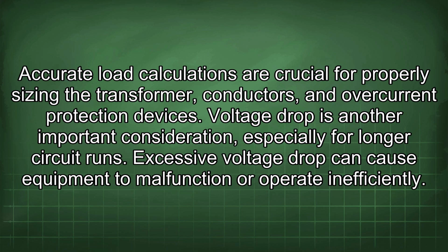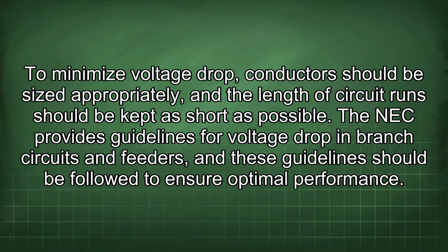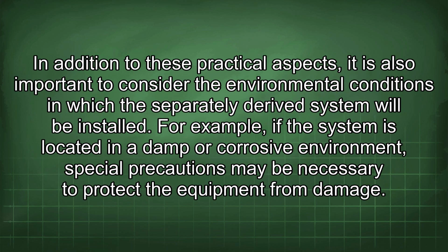Voltage drop is another important consideration, especially for longer circuit runs. Excessive voltage drop can cause equipment to malfunction or operate inefficiently. To minimize voltage drop, conductors should be sized appropriately, and the length of circuit runs should be kept as short as possible. The NEC provides guidelines for voltage drop in branch circuits and feeders, and these guidelines should be followed to ensure optimal performance.